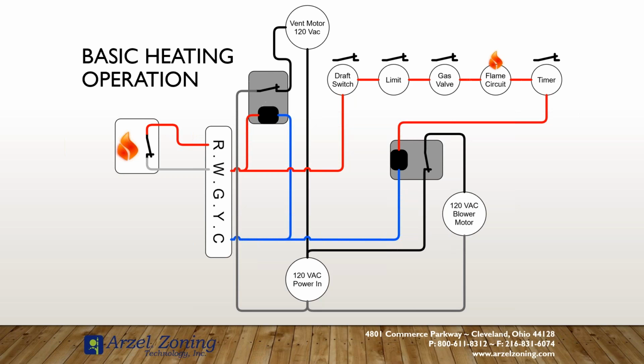So from my call for heat, my vent motor starts. My vent motor proves my draft switch. My control board also proves my limit. If my limit is open, it's not going to allow the gas valve to start. So if my limit switch is closed and my draft switch is proven closed, my gas valve is then energized. And then there's another circuit, the flame proving circuit. We call it flame rectification. That determines that there's a proven flame. If there's a proven flame, a fan timer starts to give that heat exchanger a chance to warm up. Once that timer is complete, my blower activation relay starts and my blower kicks on.